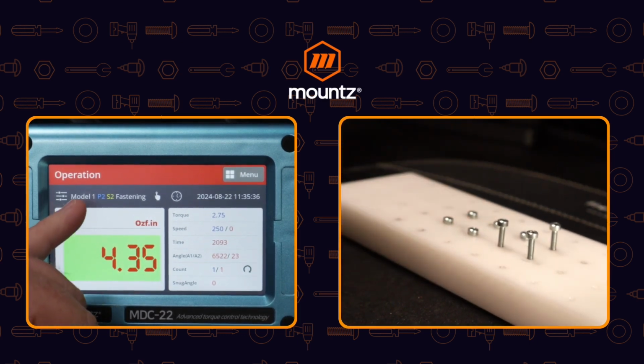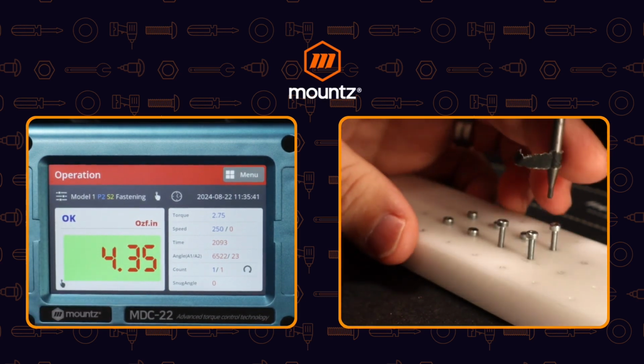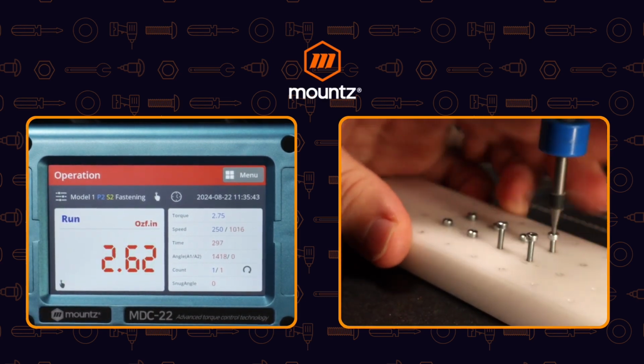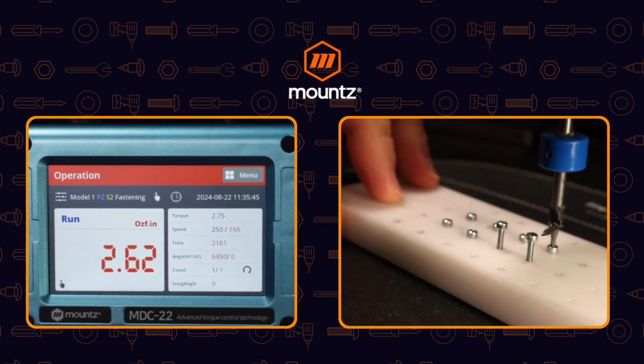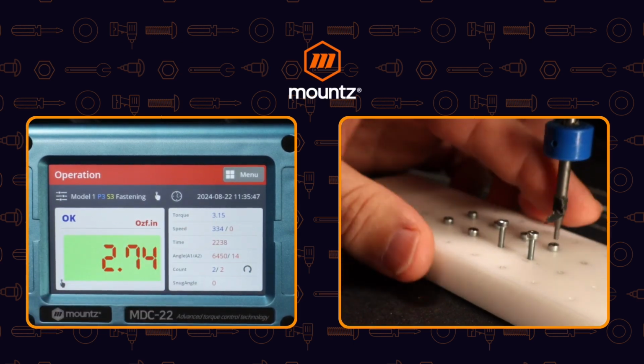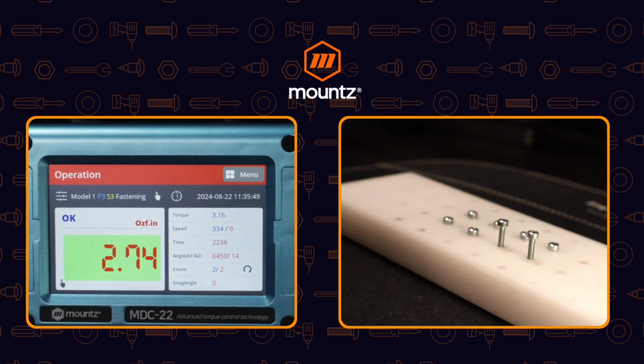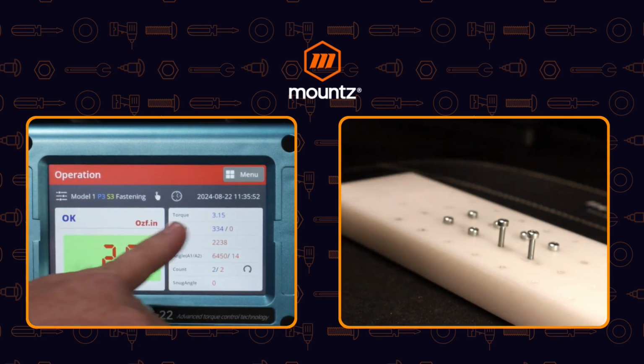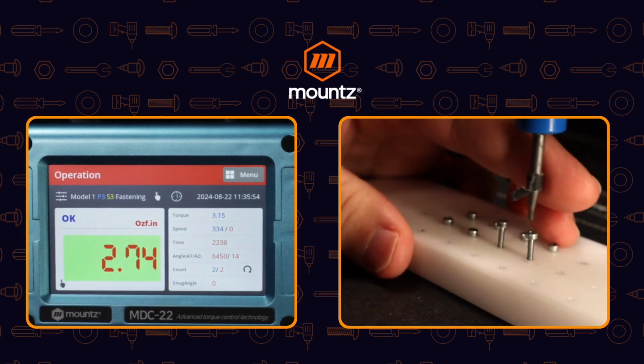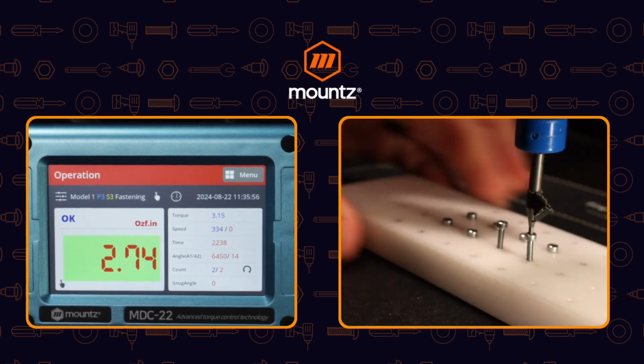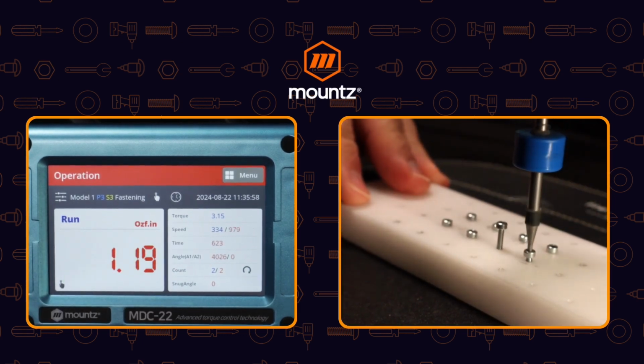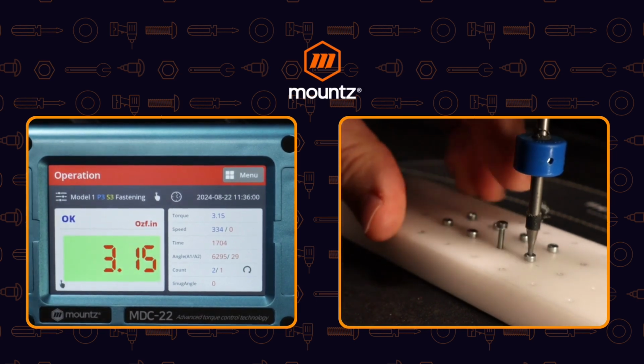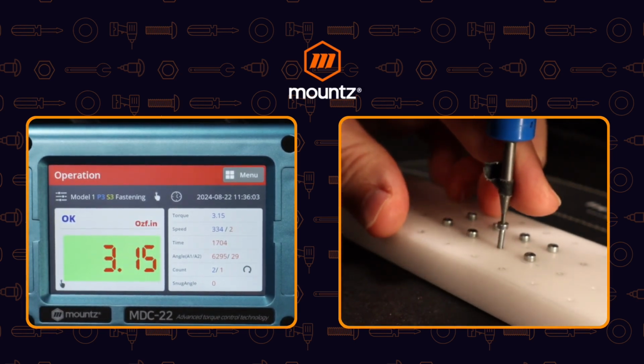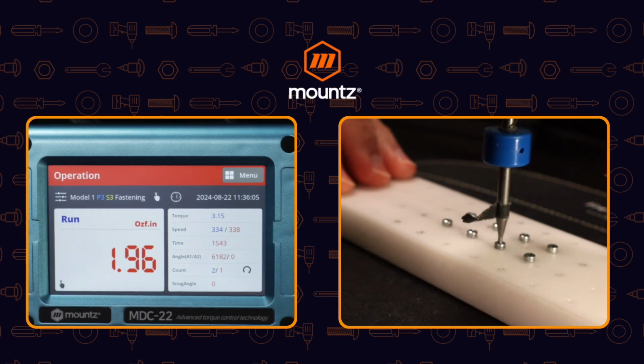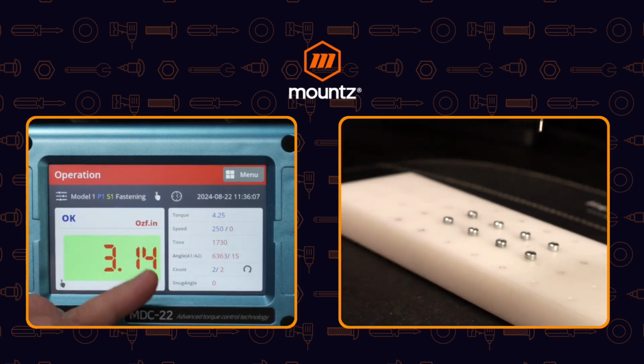And now we've changed to preset number 2 and our second step in our rundown. This one has a different torque value at 2.75 inch ounces. And now we've changed to preset 3, which has a preset value at 3.15. And the model is now complete.